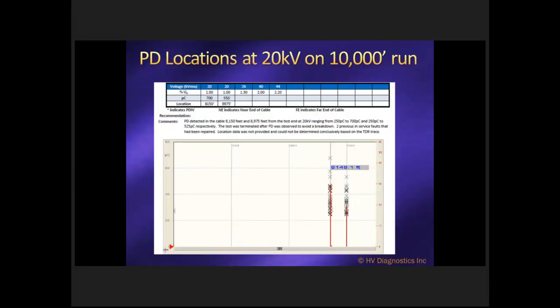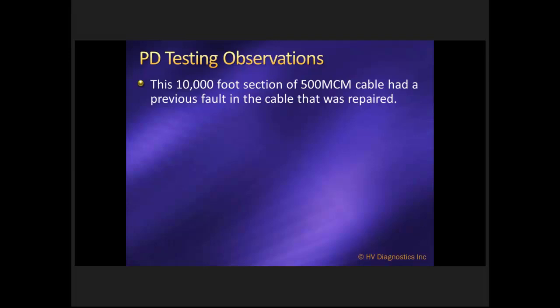When we do what we call a mapping diagram, you can see over here the two locations of PD sites in the cable, the one at 8,148 and then the other one over here. As you can see very clearly, on an otherwise completely clean cable, there are two distinctive PD sites. Alright, so let's look at the observations. This 10,000 foot cable was 500 MCM. And interestingly enough, this was one of the cables that had one of those four faults that occurred during the two to three years of the wind farm being in operation.